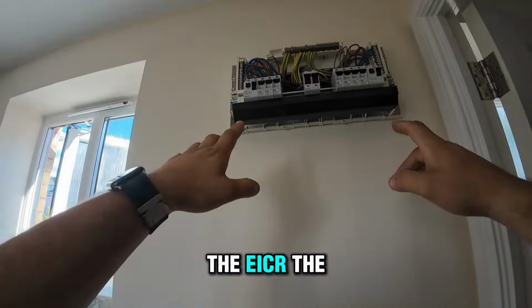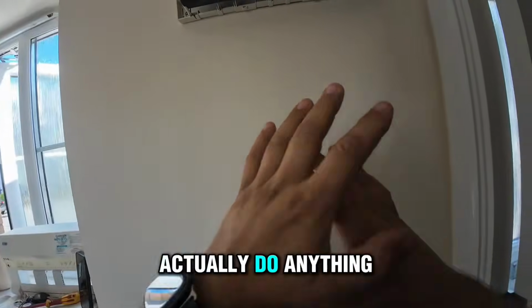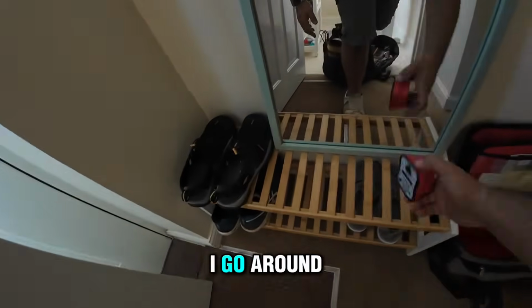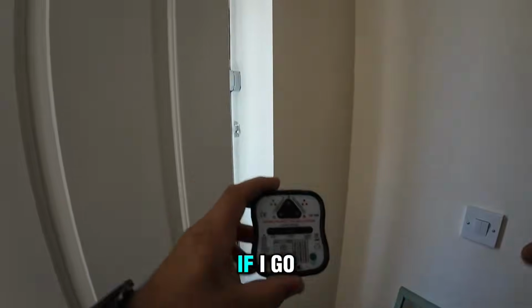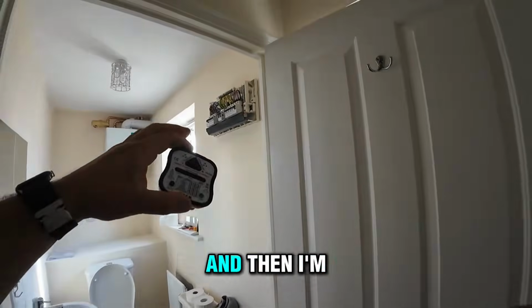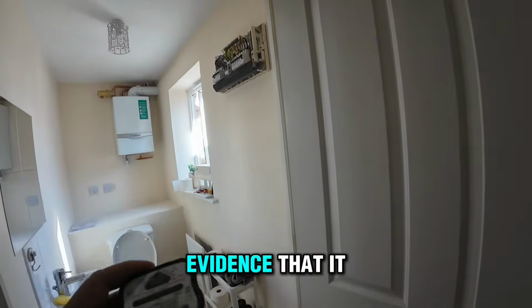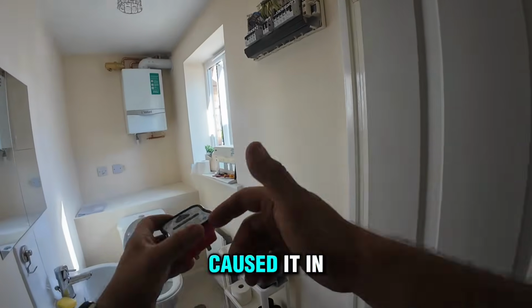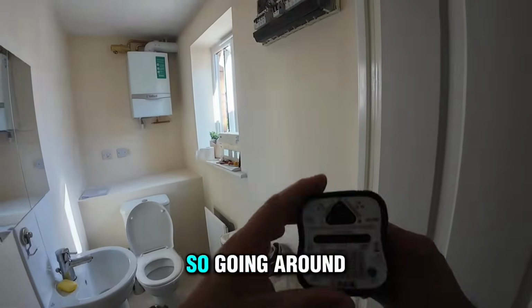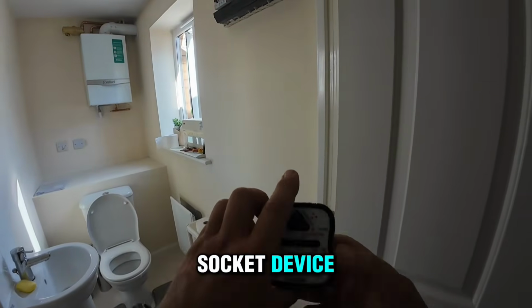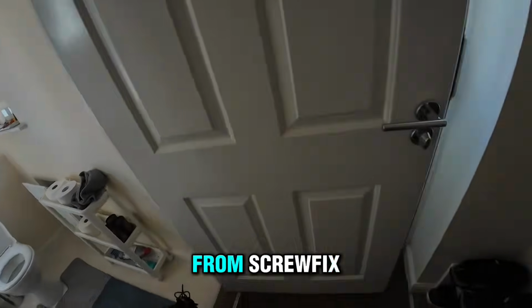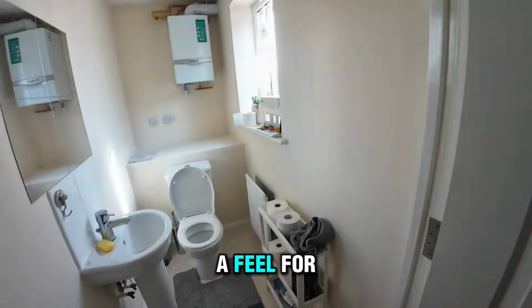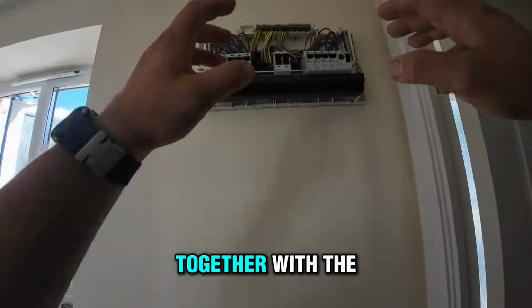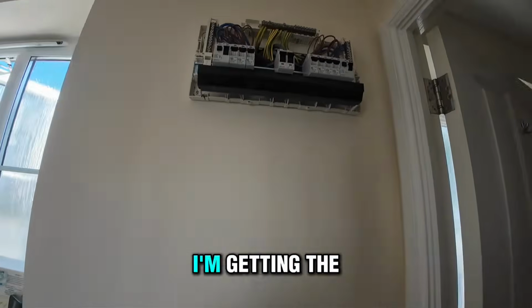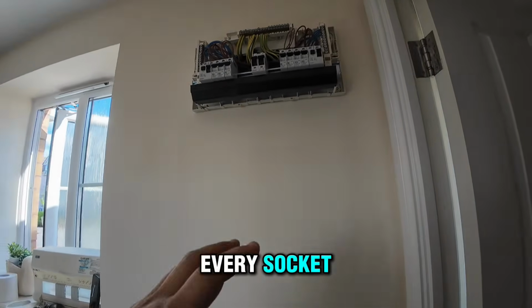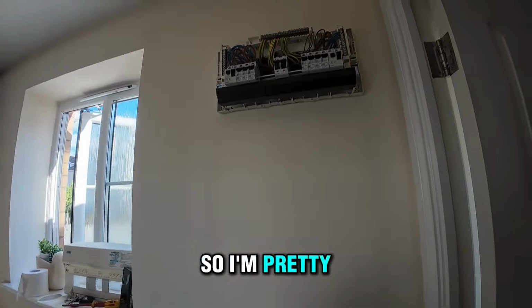Nice. The EICR, the first thing I do before I actually do anything, I've got this tiny little device. I go around, push it into every little socket. If I start taking this fuse board apart, then I'm going to find a problem. I have no evidence that it wasn't me who caused it in the first place. What have I done? So going around the house using such a little socket device, these are maybe 20-50 pounds from Screwfix. It's giving me a feel for the installation. Like this one, together with the board, it looks like no one's touched this. I'm getting the socket tester in every socket. It feels really, really good. So I'm pretty good about that one.